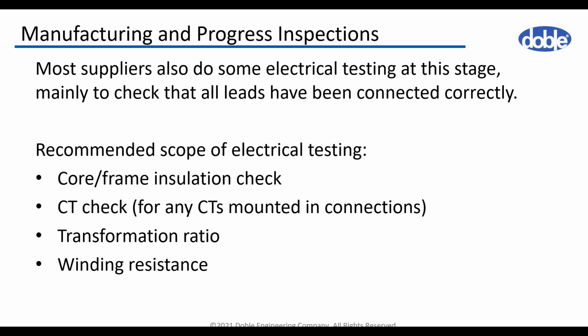The manufacturers perform electrical measurements during assembly. The purpose is to check if all the connections are made correctly and all leads are connected to the correct place or to the correct terminal. The tests which we consider useful at that stage include transformer turn ratio, winding resistance, core frame insulation resistance, and maybe a CT check if we have current transformers already mounted.